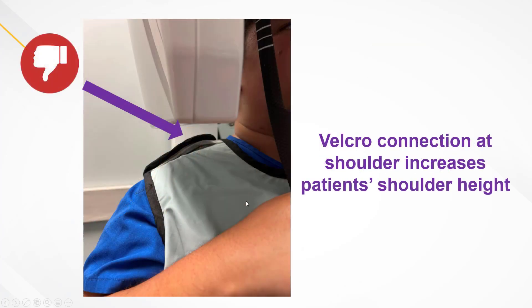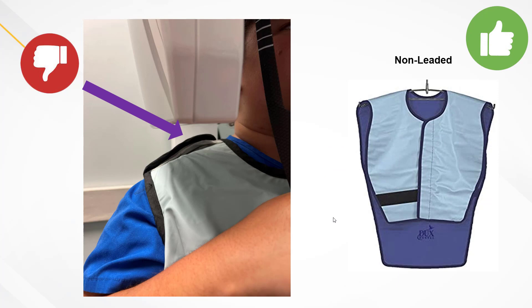Here's something you definitely want to consider. Those lead aprons that have the junction or connection point at the shoulders — you can see in this example we're losing roughly an inch of clearance space for the machine to rotate around. That could mean a lot, so be conscious of that. Double-check what you're using in the practice. A much better option, in my opinion, is to use a non-leaded apron. Number one, it's a lot lighter for your patients. And number two, it connects in the front using Velcro and sits flatter on the patient's shoulders, giving you as much clearance as possible. All these little tips are even more important when it comes to your necklace patients — meaning patients with no neck.